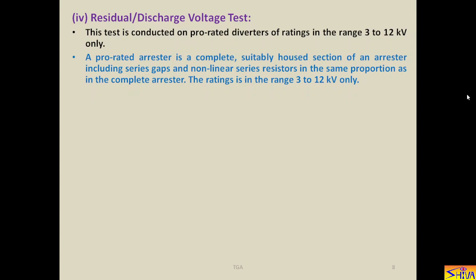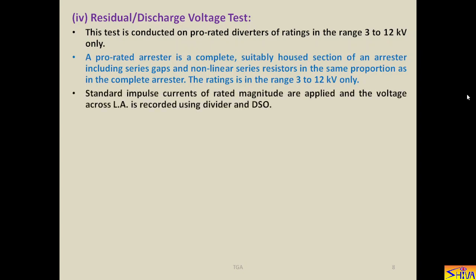So we are designing a lightning arrestor which is rated for low voltage, that is in the range of 3 to 12 kV. But in this lightning arrestor, series gaps and non-linear series resistors are in the same proportion as in the complete arrestor. Standard impulse currents of rated magnitude are applied and the voltage across the lightning arrestor is recorded using a voltage divider and digital storage oscilloscope. The magnitude of the current is 0.5, 1 and 2 times the rated current.